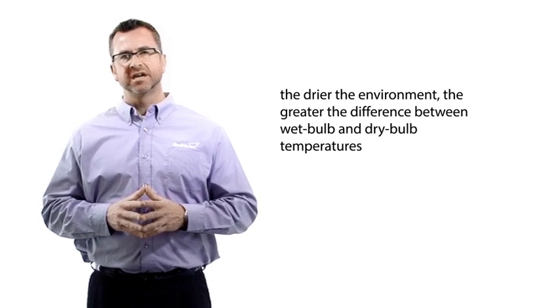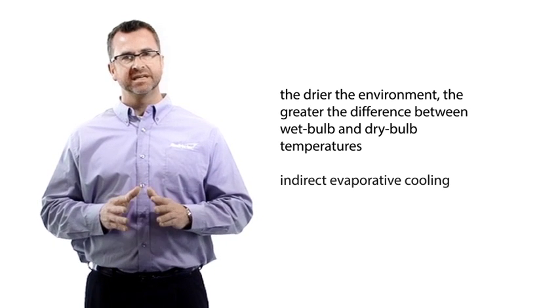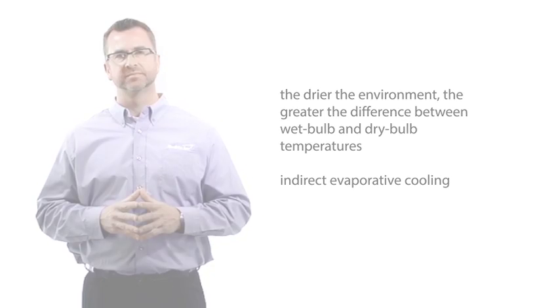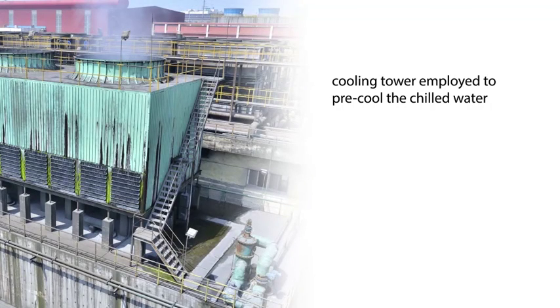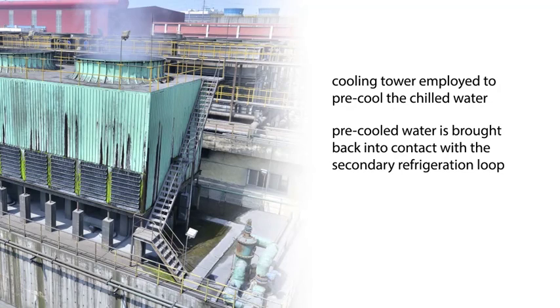Water-side economization is essentially indirect evaporative cooling. The cooling tower in a water-chilled system is employed to pre-cool the chilled water to nearly the wet bulb temperature of the air. That pre-cooled water is then brought back into contact with the secondary refrigeration loop within the facility.